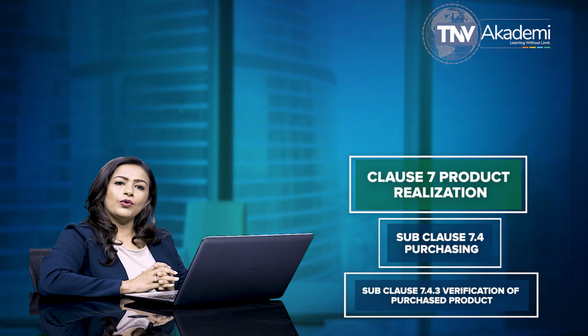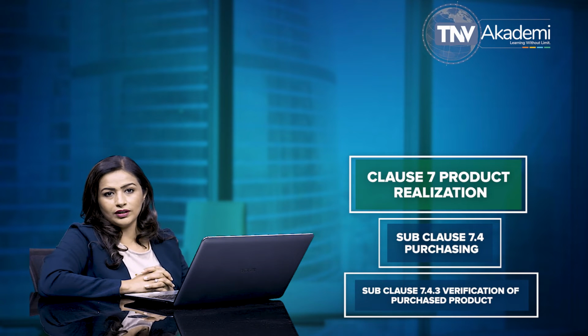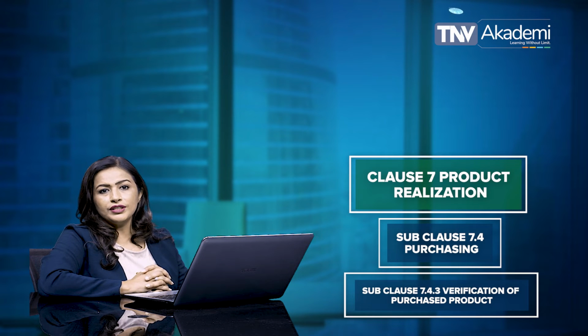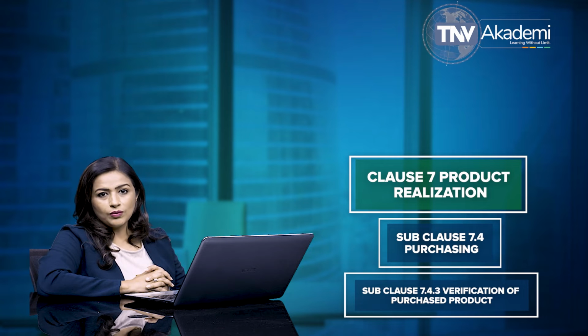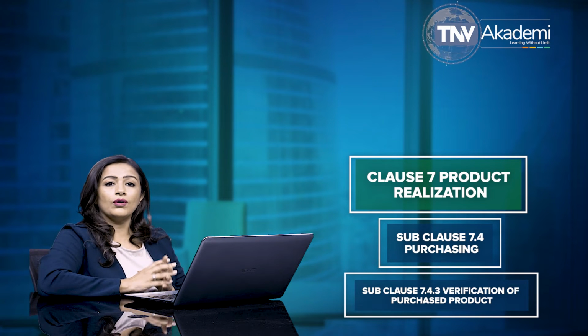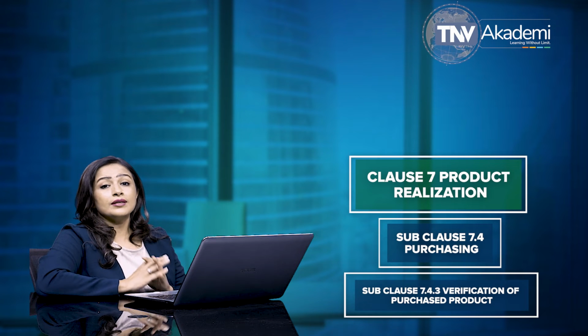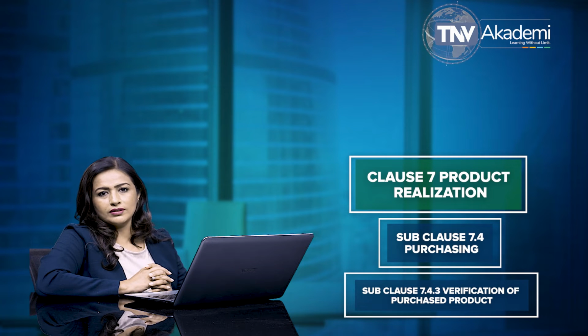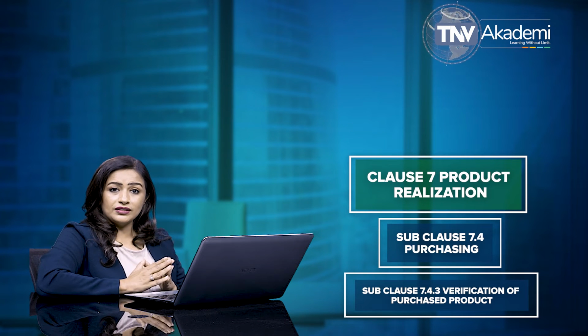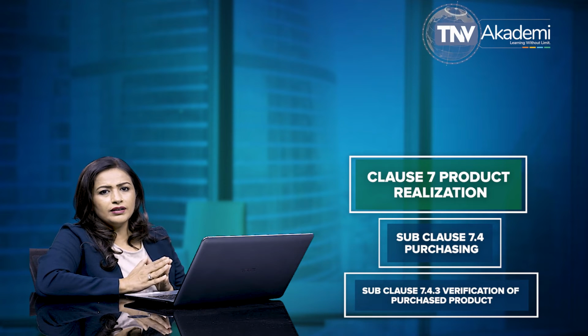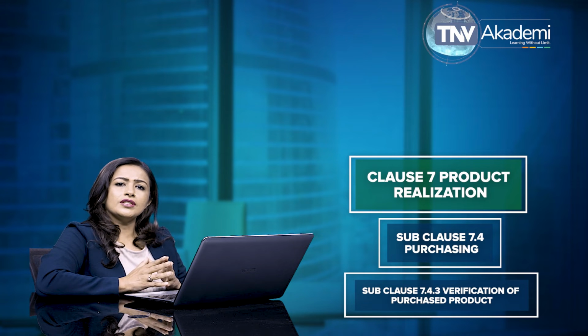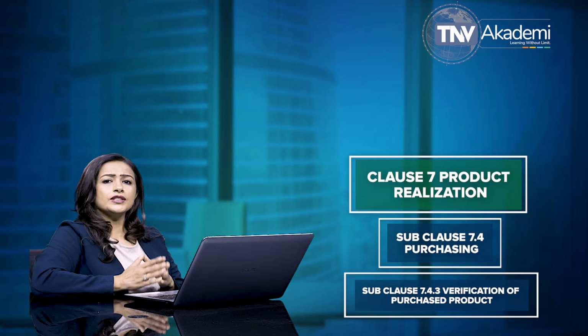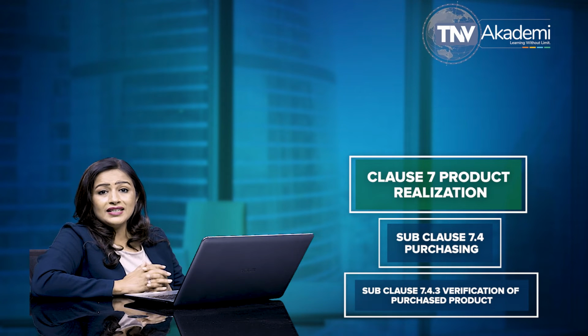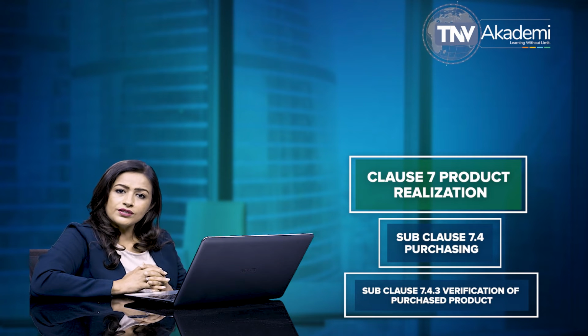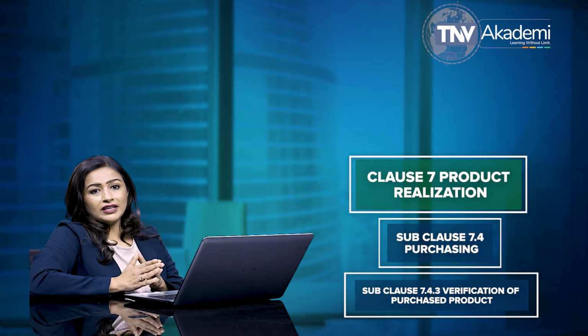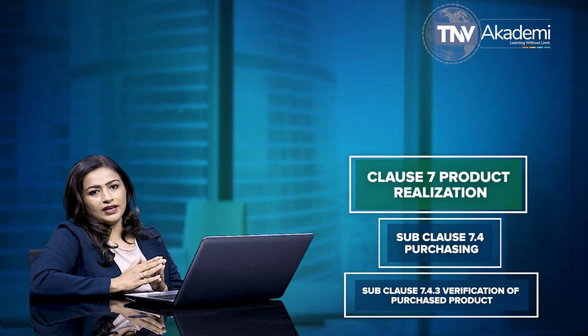Coming to subclause 7.4.3, verification of purchased product. This subclause 7.4.3 of the standard specifies that the organization is required to establish and implement the inspection or other activities necessary for ensuring that purchased product meets specified purchasing requirements. This clause says that the extent of verification activities is required to be based on the supplier's evaluation results and proportionate to the risks associated with the purchased product. As per this subclause, when the organization becomes aware of any changes to the purchased product, the organization is required to determine whether these changes affect the product realization process or the medical device.